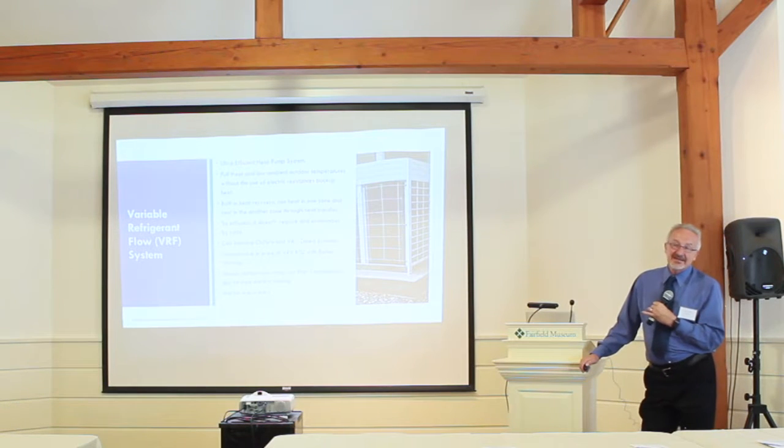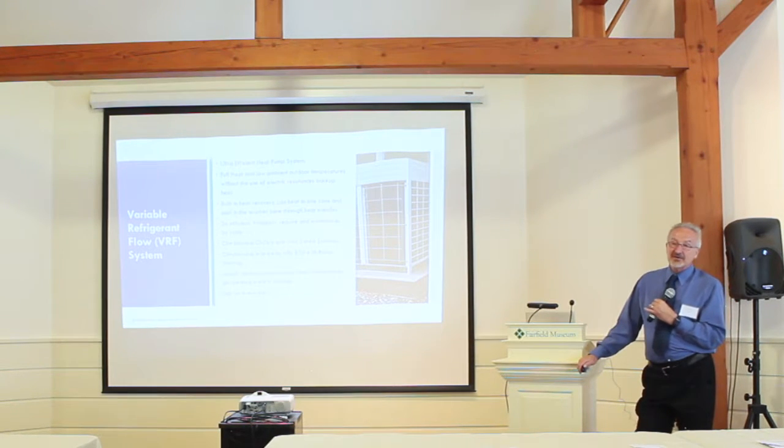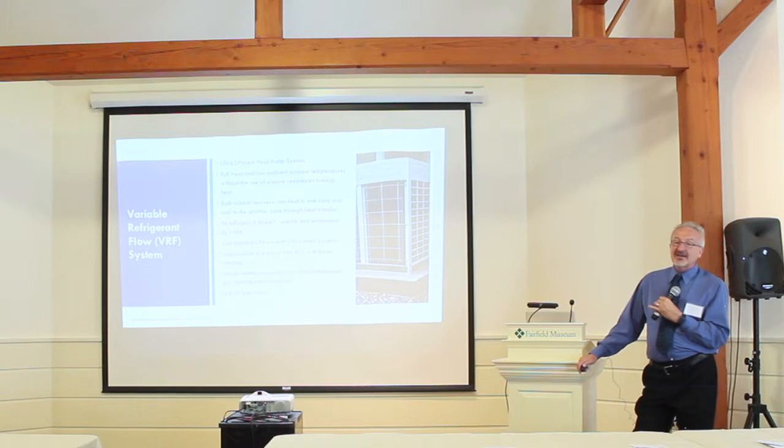A lot of manufacturers, you're going to be seeing VRF systems in a lot of buildings. We're doing a 50,000 square foot office building right now, all VRF, and modeling it compared to a high efficiency boiler system, and it came out 10-20% better.